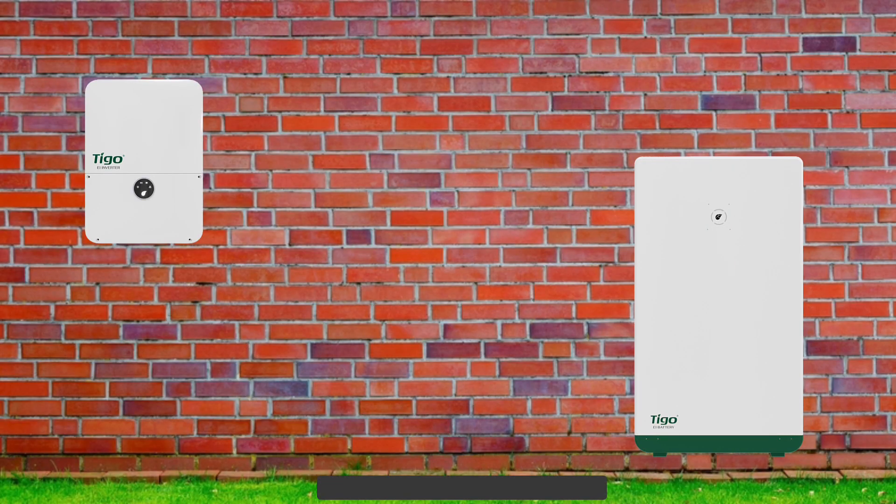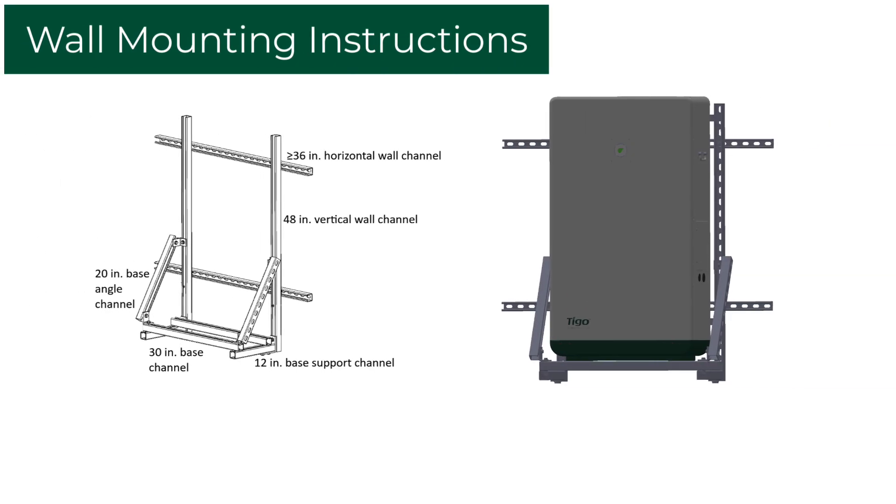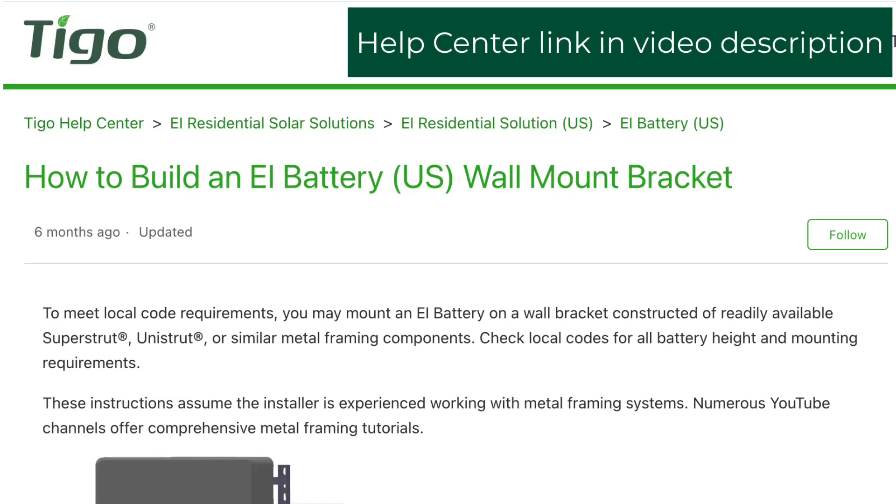Place the battery cabinet on a foundation for a ground-mounted application. The battery cabinet should not be further than seven feet away from the Tigo inverter. The battery may be wall-mounted using the appropriate hardware and verified by an engineer. Contact the Tigo customer success team if you have any questions about mounting.